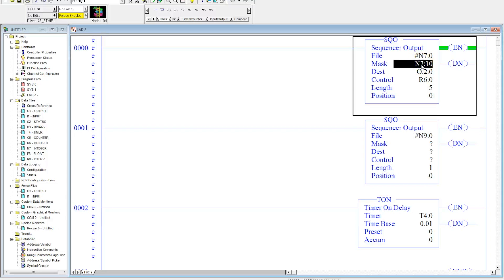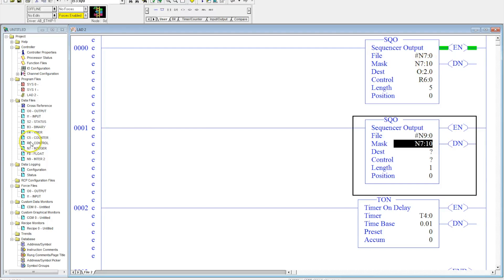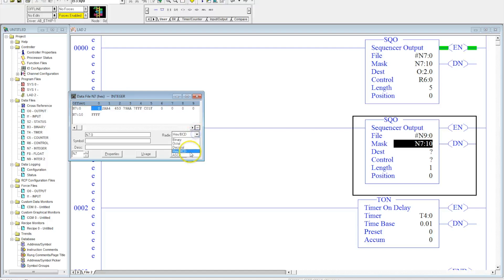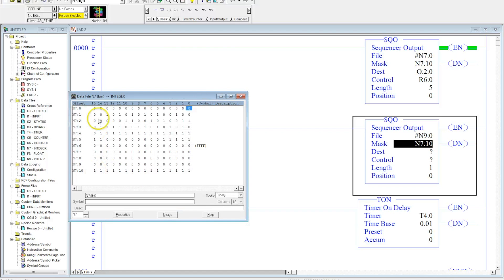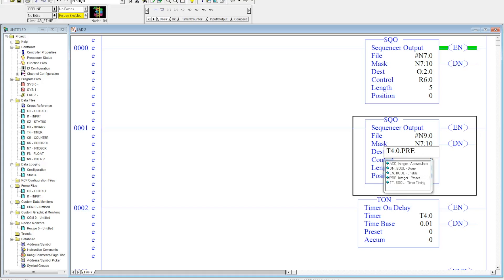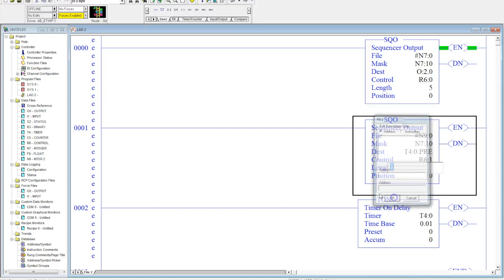Now I'm going to start to program this in a very similar way that I did our output instruction. This is going to be N9:0, the mask I'll use the same as before — N7:10. I checked it and it's binary with ones across the board, so all of the bits will flow down to the output instruction. My destination is going to be T4:0.PRE, which is the preset for this timer. My controls I'll make R6:1 and the length I'll make five.